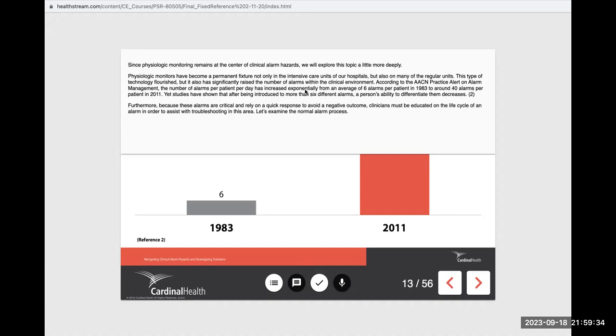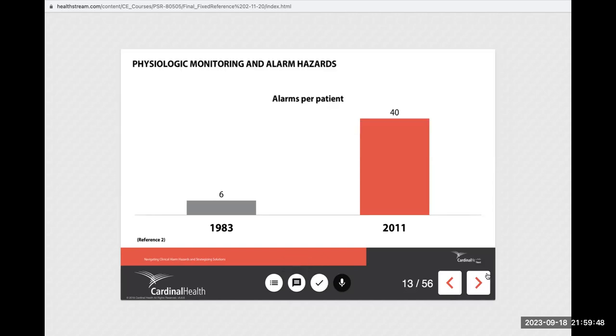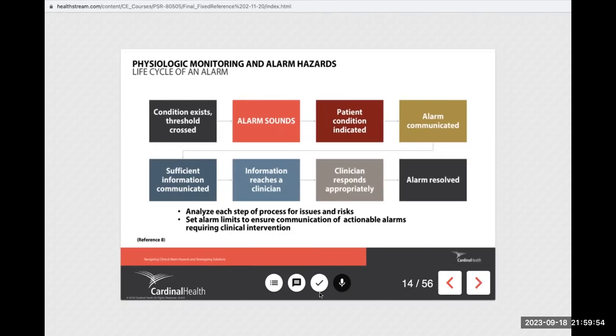Furthermore, because these alarms are critical and rely on a quick response to avoid a negative outcome, clinicians must be educated on the life cycle of an alarm in order to assist with troubleshooting in this area. Let's examine the normal alarm process. This process begins when a condition crosses a preset threshold, triggering the alarm. It continues until there is resolution of the alarm.